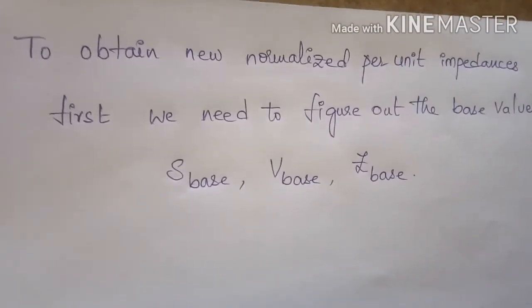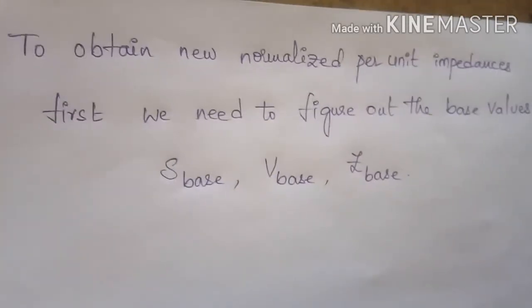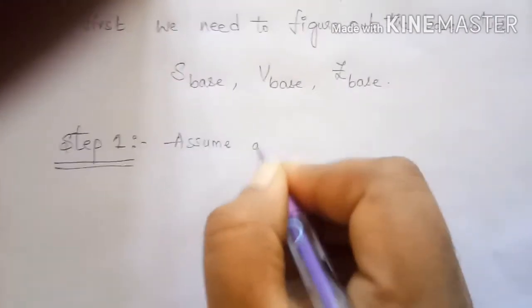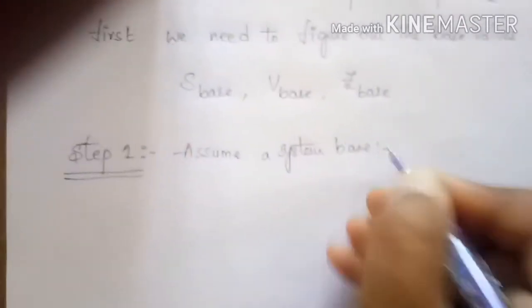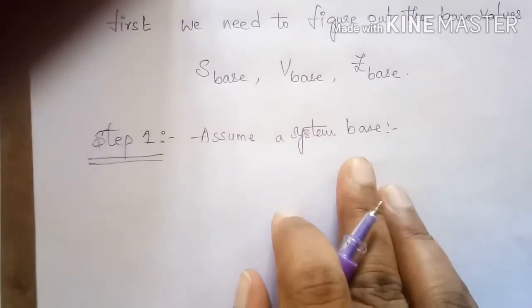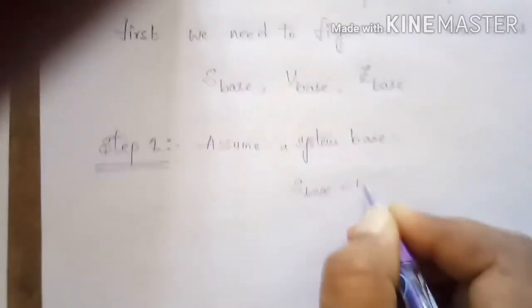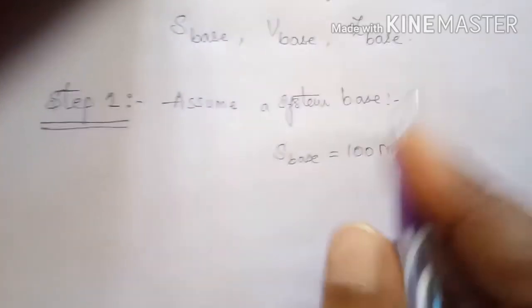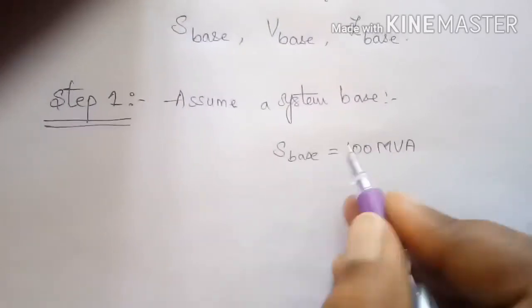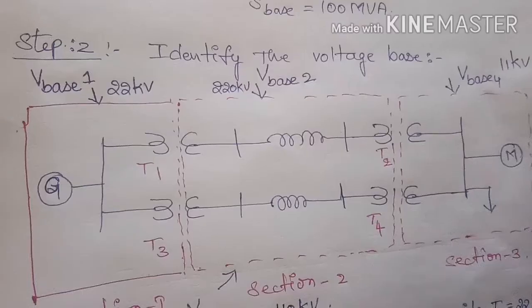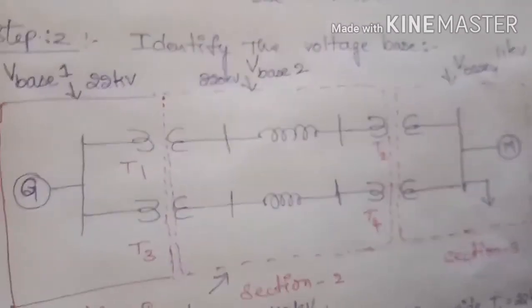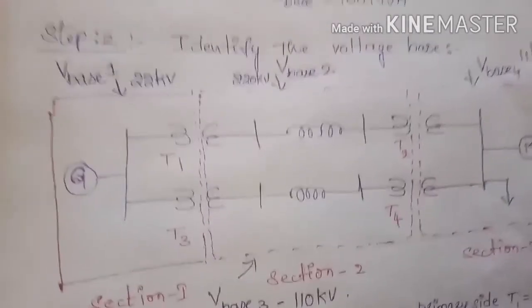To obtain new normalized per unit impedance values, we first determine the base values: S base, V base, and Z base. The first step is to assume a system base. The system-wide S base is taken as 100 MVA. This is a random assumption chosen to make calculations easy.